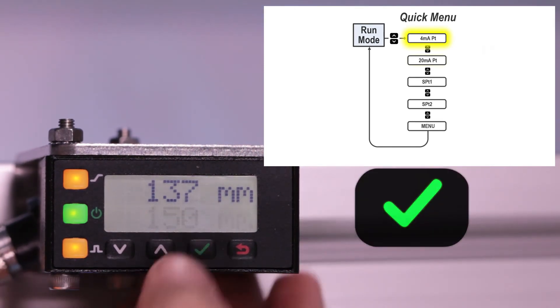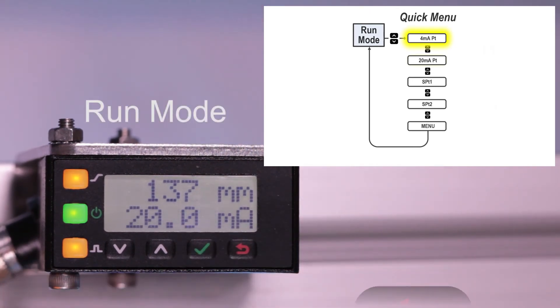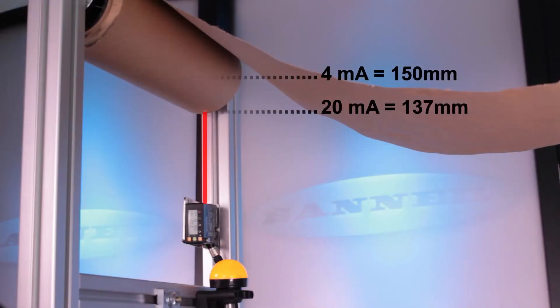Because the core diameter is known to be at 150mm, the 4mA point can be set at 150mm without having to unwind the roll to present a target.